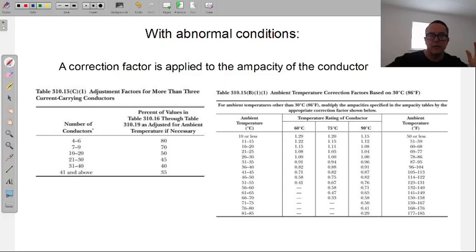You got a 100-foot conduit run. Where does the heat in the center of that run go? Nowhere. It stays in the conduit, and it's going to affect the wire's ability to carry amperage. This wire cannot carry the same amount of amperage anymore by factors that we can multiply. So if we have too many wires, we start to add a correction factor for too many wires.